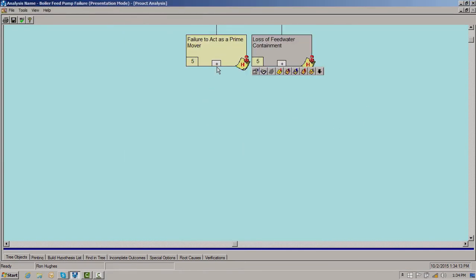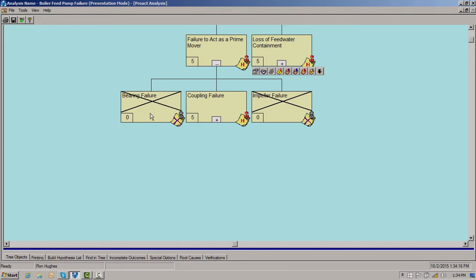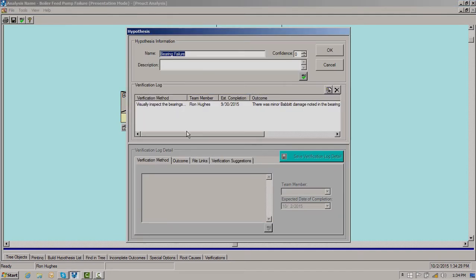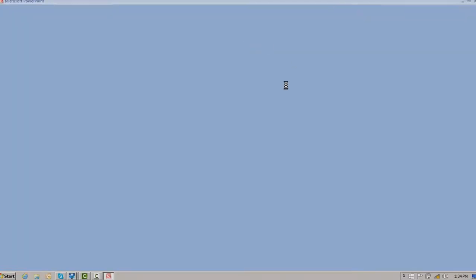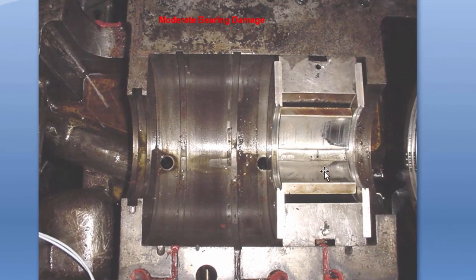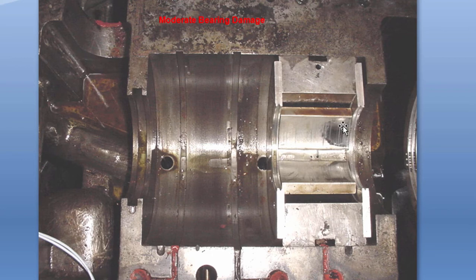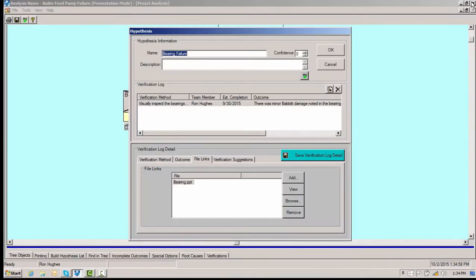We'll look at failed to act as a prime mover. How can that be? Well, either we've got a bearing failure, a coupling failure, or an impeller failure. We opened up the pump — the housing was fine, the impeller was fine. For the bearing, we do a visual inspection. What you're going to see here is some moderate damage to the bearing — this is Babbitt over here. There's just not enough damage there to cause the failure we're investigating. We can attribute the damage we see to a result of the failure, definitely not a cause. So it's not a bearing failure.